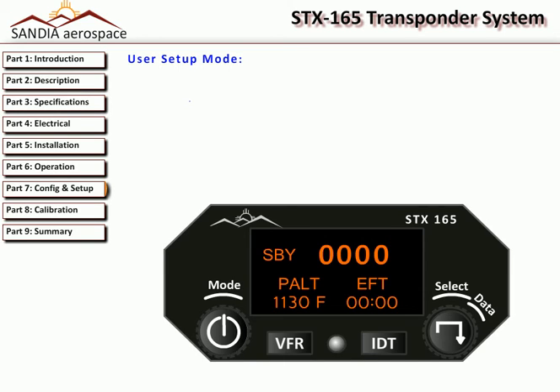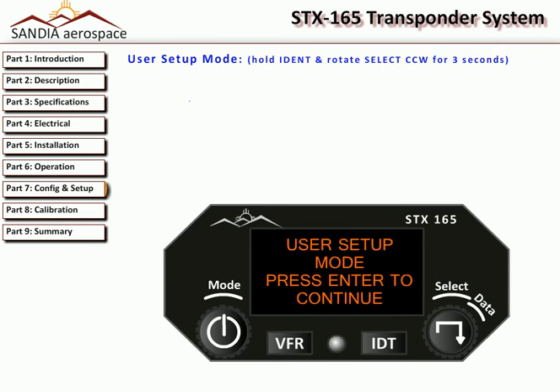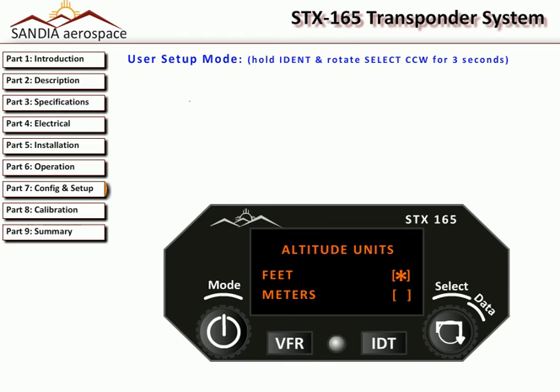To access this mode, apply power to the unit and make sure the operating mode is set to standby. Press and hold the ident button while rotating the select knob counterclockwise against its stop. Continue holding the ident button and hold the select knob against the stop for 3 seconds or until you see User Setup Mode displayed. Now press the Enter button. This will enter the user setup mode.